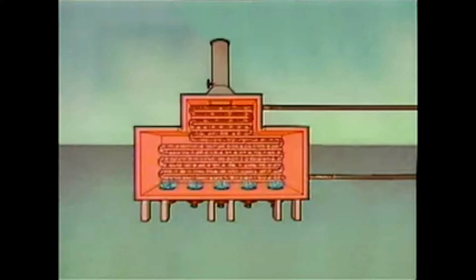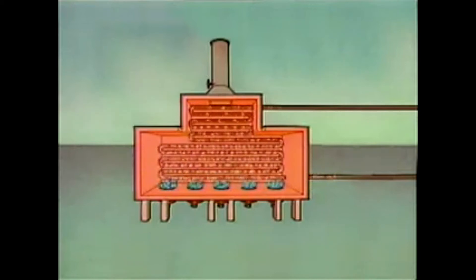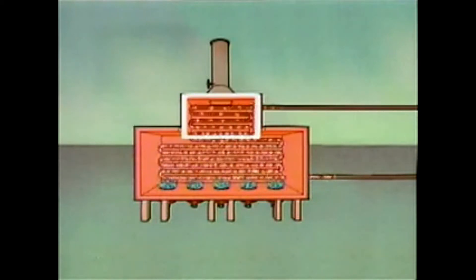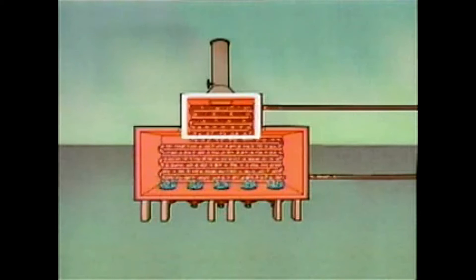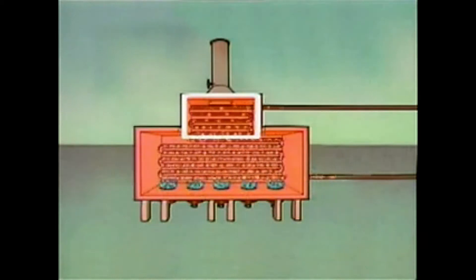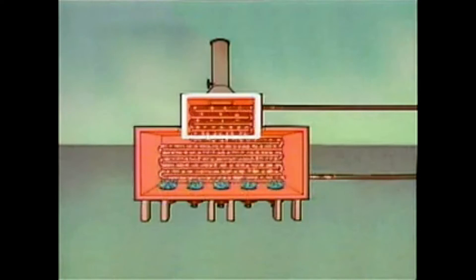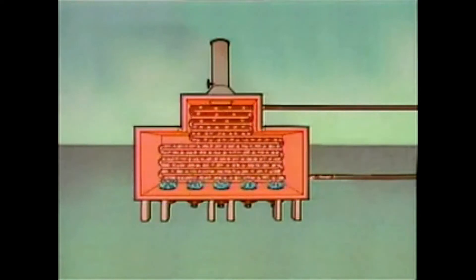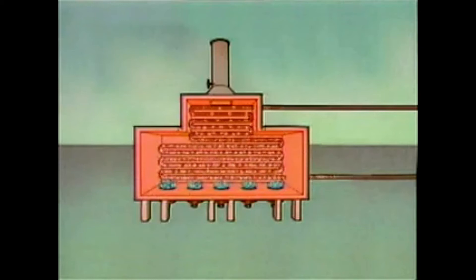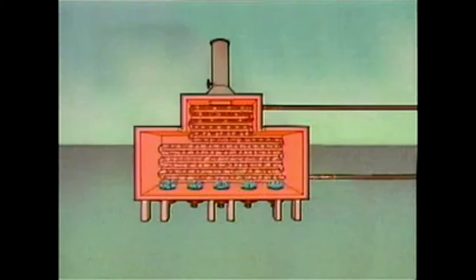Furnaces are used to heat many different types of process fluids. As the process fluid circulates through the tubes inside the furnace, it receives heat that is produced by burning fuel. The process fluid enters the furnace through the tubes in the convection section. This arrangement allows the fluid to be preheated by the combustion gases before it reaches the radiant section of the furnace. Preheating the process fluid makes it possible to bring it up to the desired temperature while burning less fuel, making the furnace more efficient.